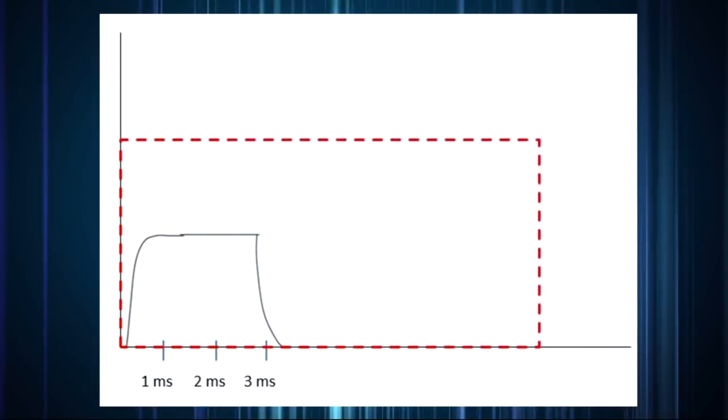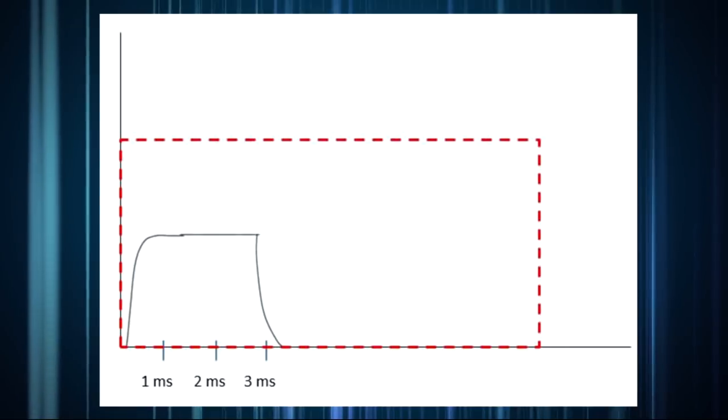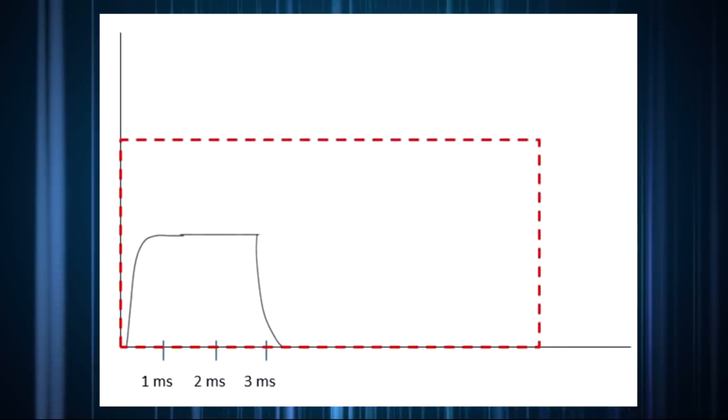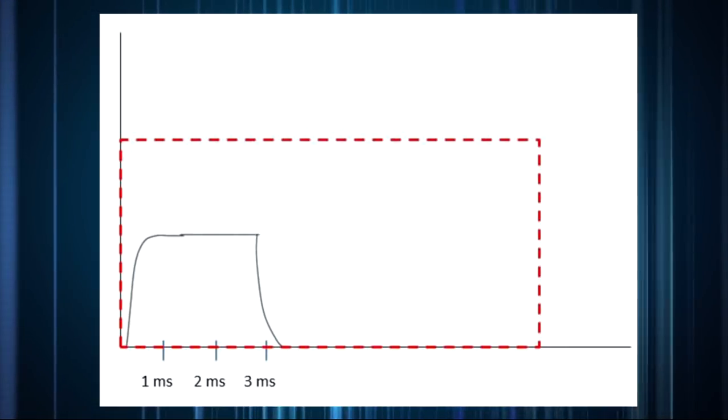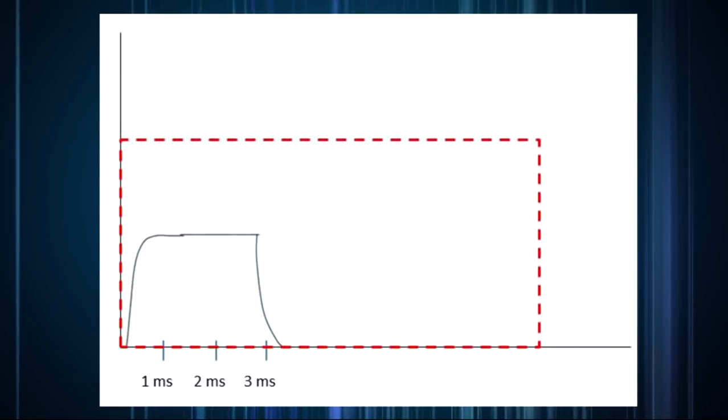If on the other hand, the maximum pulse width setting is set to much longer than the actual laser pulse width, that's going to allow some extra noise to get in. In general, one should choose the shortest maximum pulse width setting that's still definitely longer than the actual laser pulse.